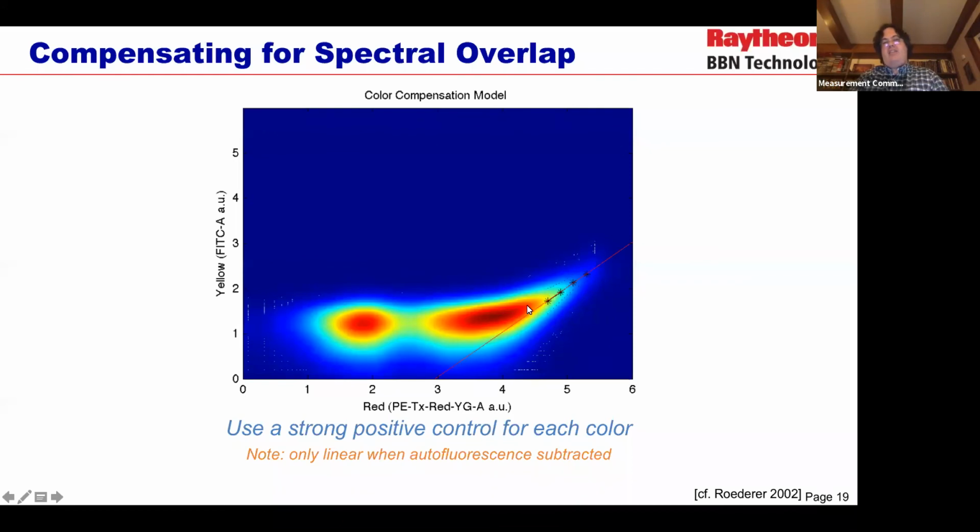In this case, we're seeing this diagonal line coming up here, and it's showing that we've got a little more than a 1 in 1,000 spillover. So this is a really pretty low level. We want to make sure it's less than 10%. I usually recommend keeping to less than 3% if you can. But often you can get combinations, like from the fluorescent proteins that the measurement committee recommends, that are extremely low indeed.